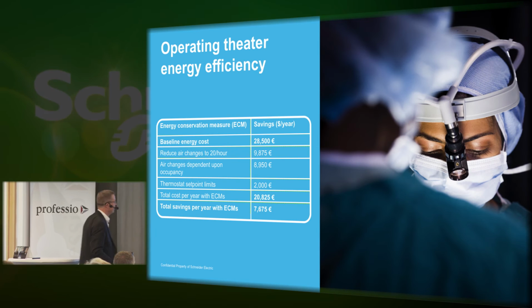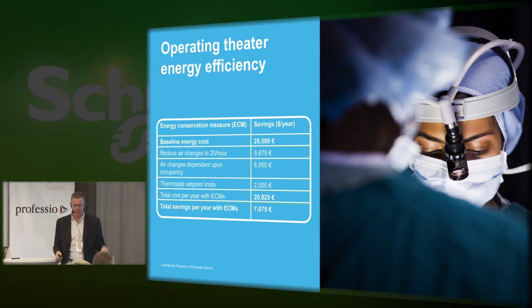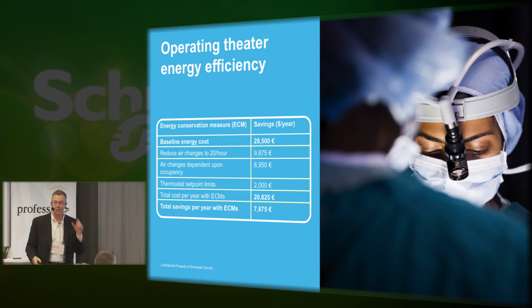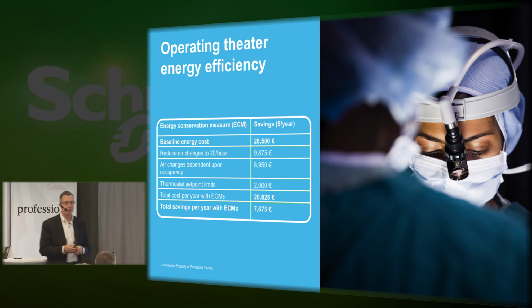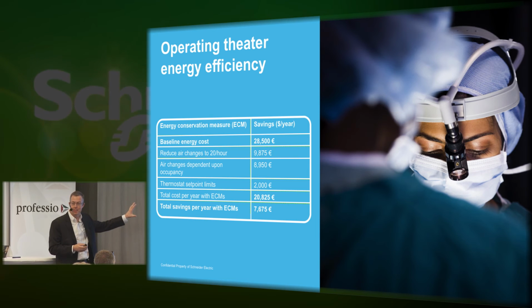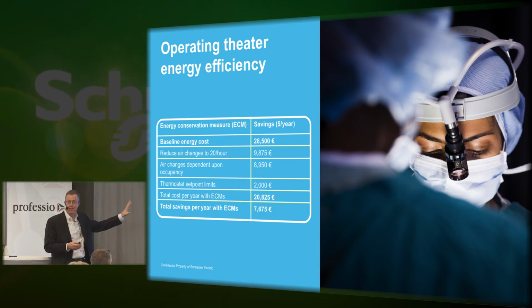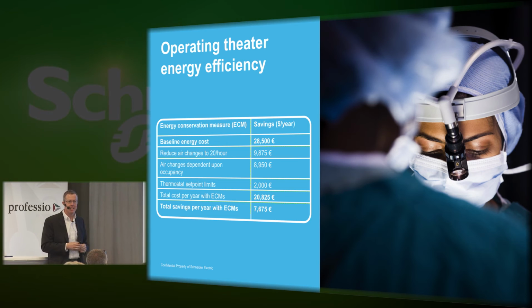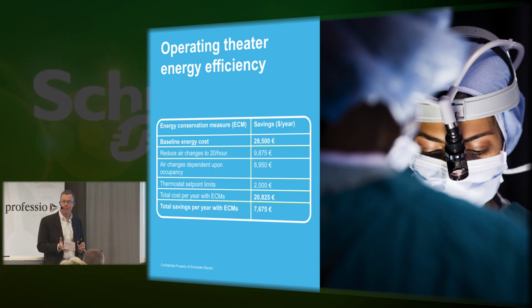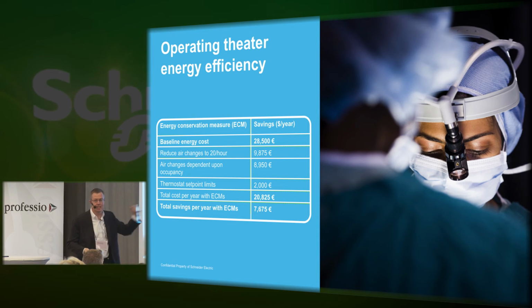Some surgeons need, depending on the procedure, certain humidity levels—it could be orthopedic work or certain glues—or certain temperatures, sometimes down to 16 or 17 degrees. But is that necessary at 3 a.m.? If you have 10 operating theaters all running at 16 degrees C with 30 air changes an hour, and they're empty, that's where intelligent setbacks come in.